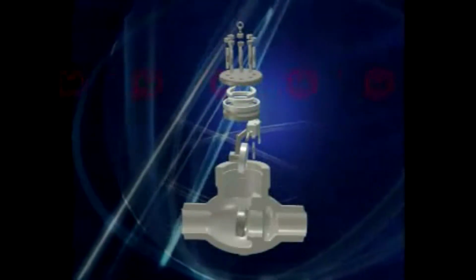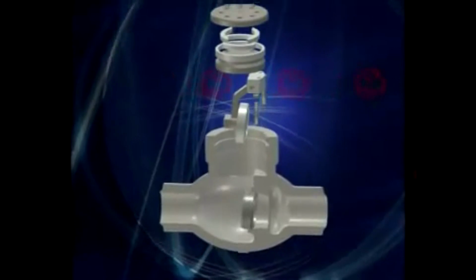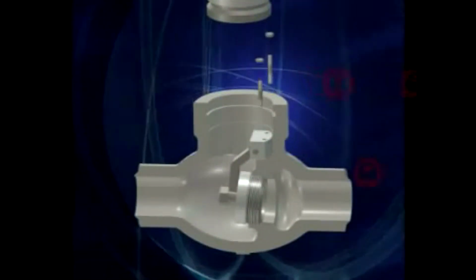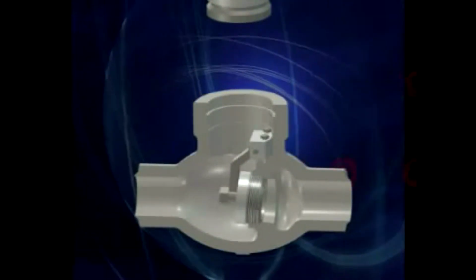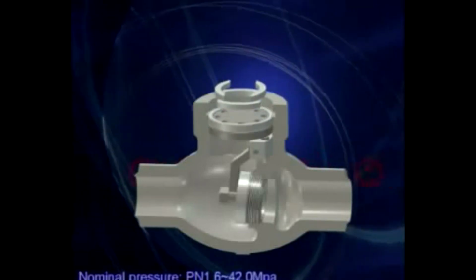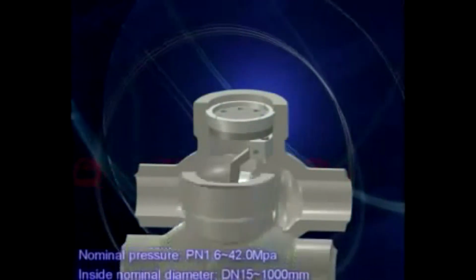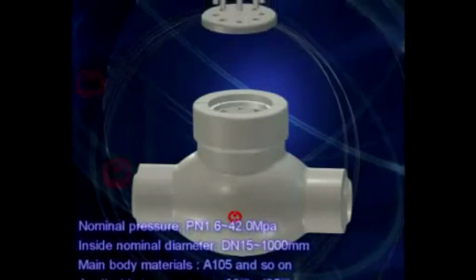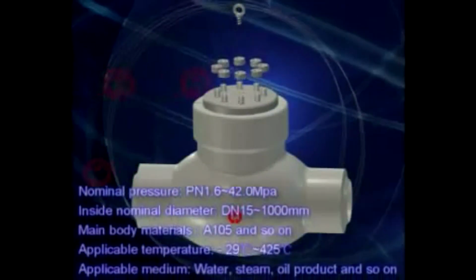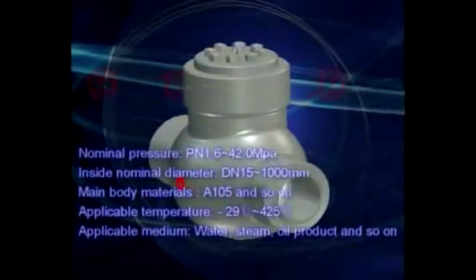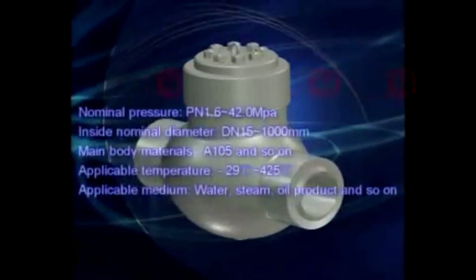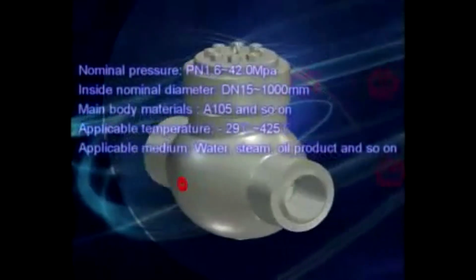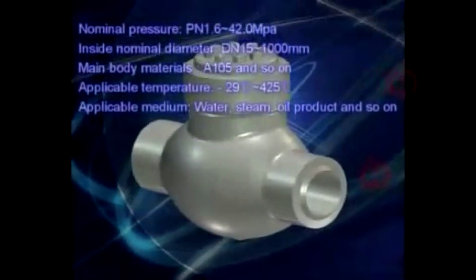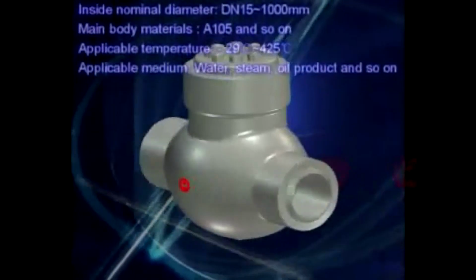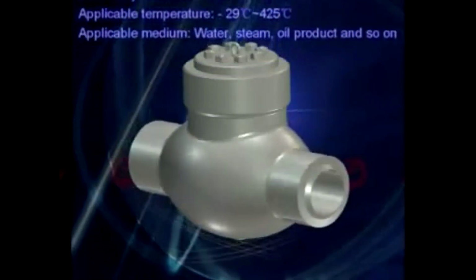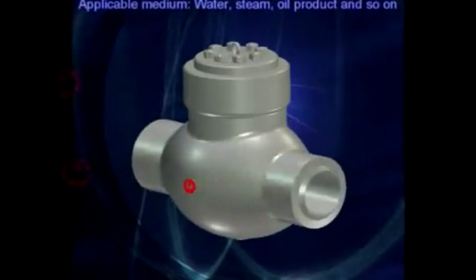Products are designed and manufactured according to standard GB/T 12236-1989. Nominal pressure from PN 1.6 to 42 MPa. Inside nominal diameter DN 15 to 1000 mm. Materials chosen for the main body are A105 and so on. Applicable temperature from minus 29 degrees centigrade to 425 degrees centigrade. Applicable medium, water, steam, oil product, and so on.